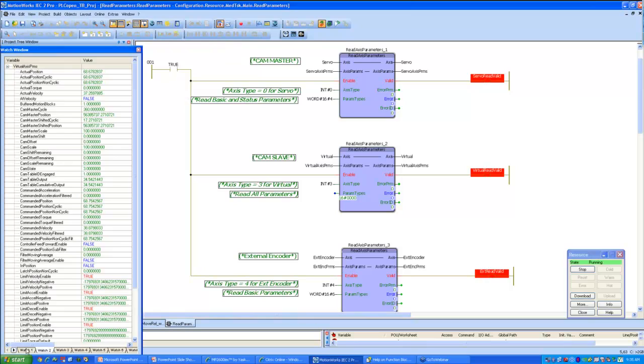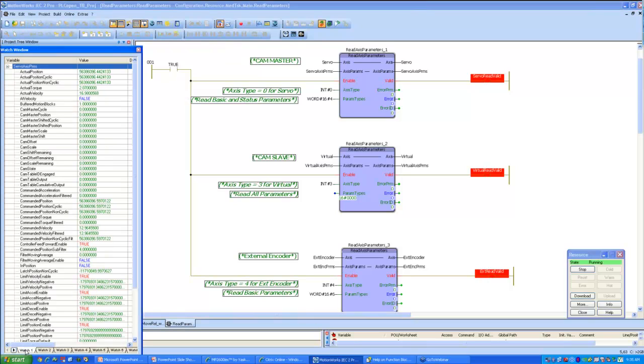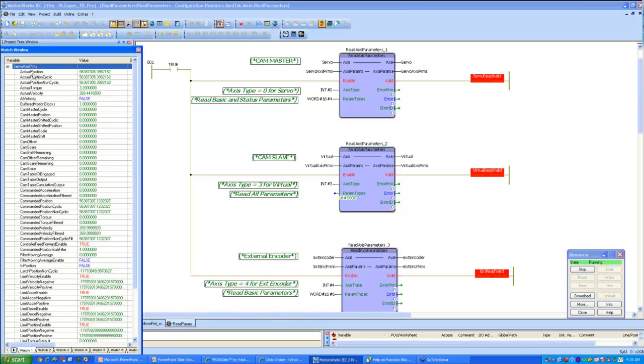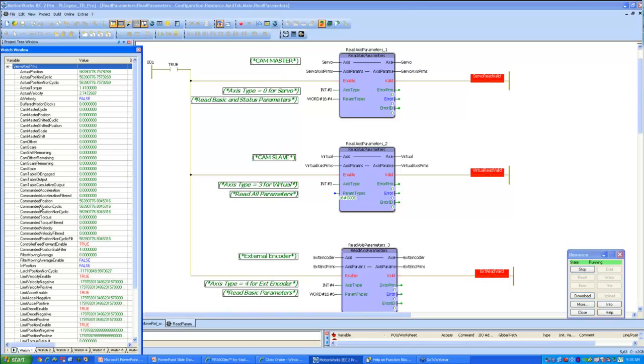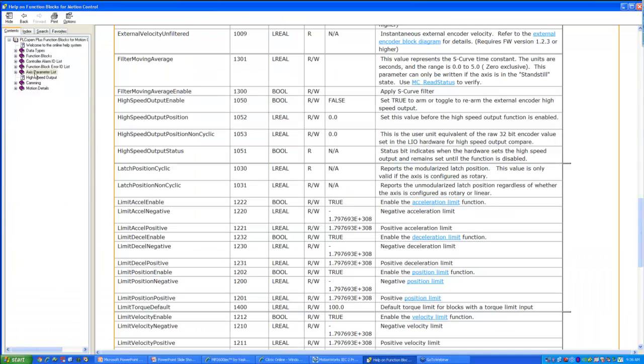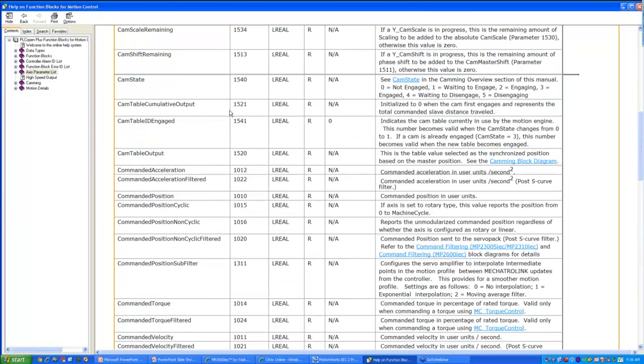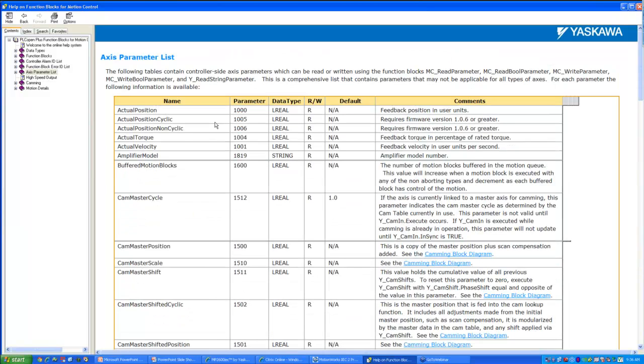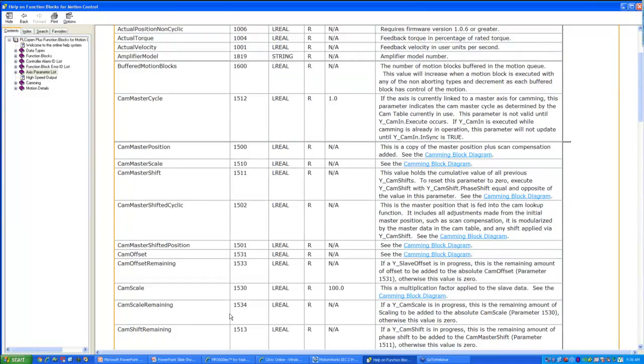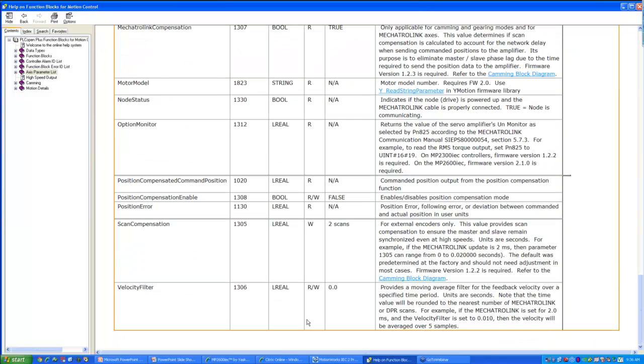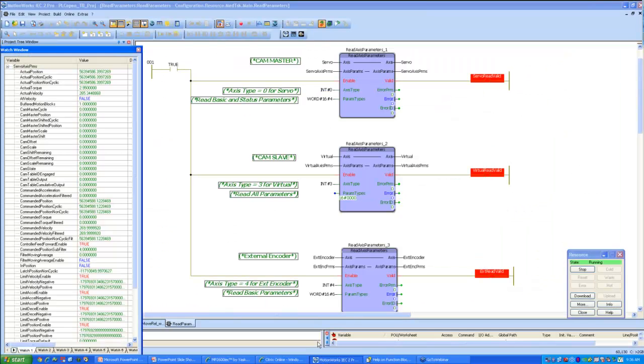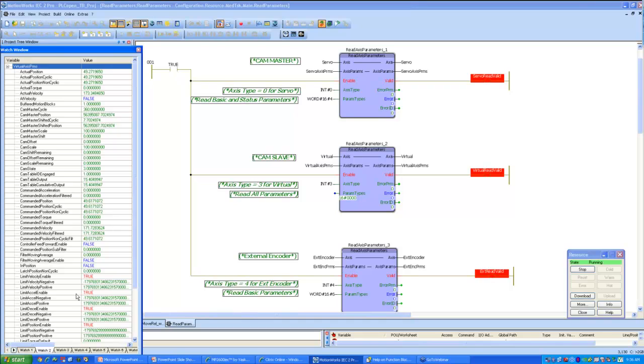Let us take a look at how these parameters show up on our watch window. This is the list of all servo parameters that I am trying to read, and you can see here it contains all basic and status parameters, actual position, and since I am commanding position for my cam master, this is basically the commanded position. And you can see here that this is a linear axis that basically keeps going in one direction. And the parameters that are being read using this function block are listed in the help manual for the software for all axes. They're listed as axis parameters, and they're in the help manual for the function blocks. And this is a comprehensive list of all the parameters that can be read for a particular axis.